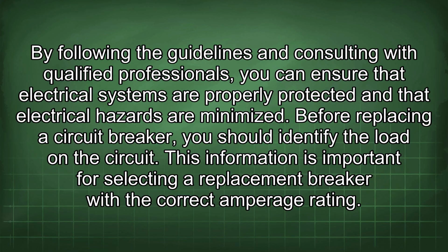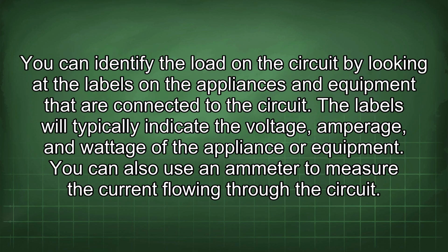Before replacing a circuit breaker, you should identify the load on the circuit. This information is important for selecting a replacement breaker with the correct amperage rating. You can identify the load on the circuit by looking at the labels on the appliances and equipment that are connected to the circuit. The labels will typically indicate the voltage, amperage, and wattage of the appliance or equipment.